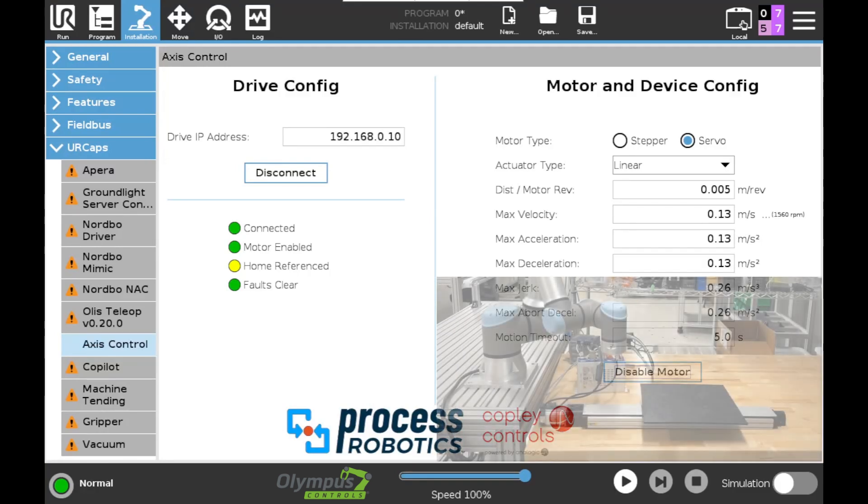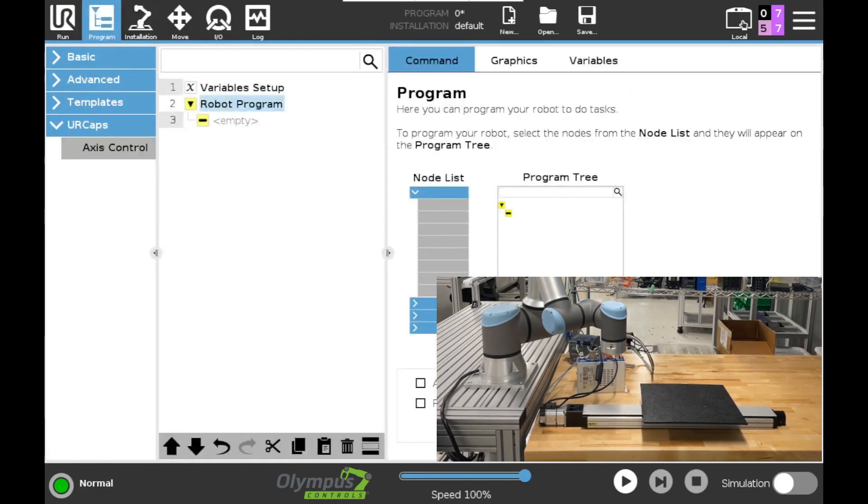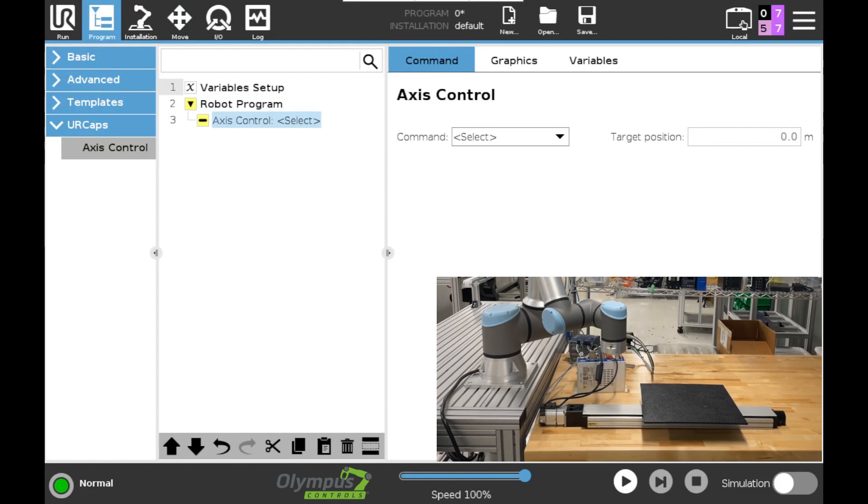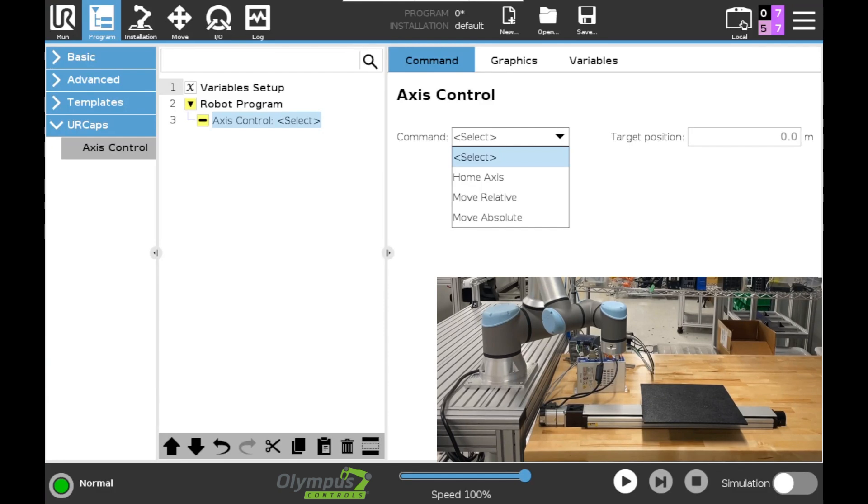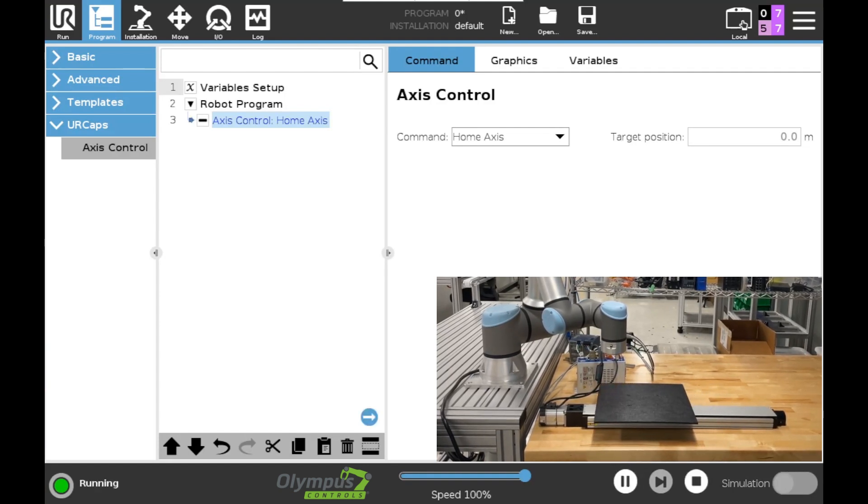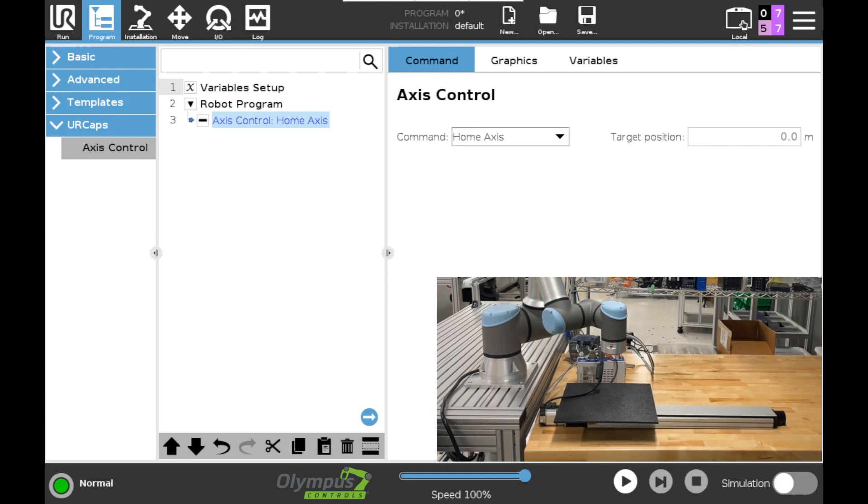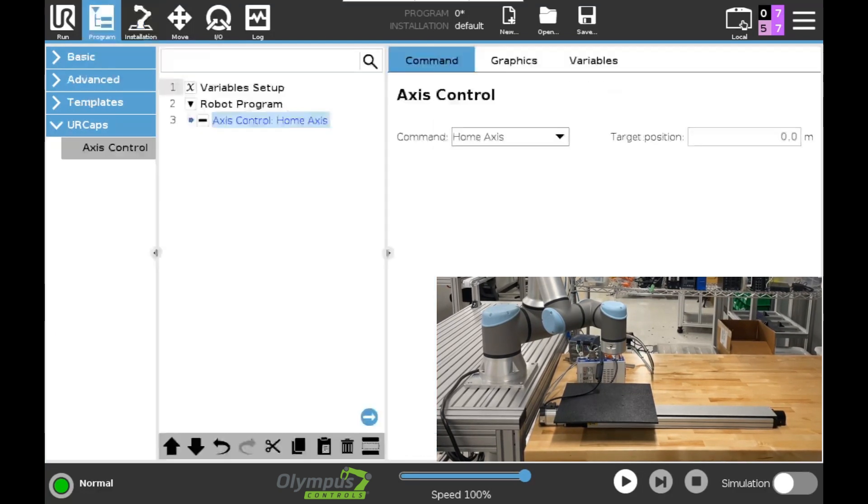In order to home the axis we'll need to actually start using our cap. And what the cap adds is a new node under the programming interface. You can see I've just added one into our blank program here. And you can see in our right panel this is what we are able to do. We can home the axis, move relative, move absolute. I know I want to home our axis and let's go ahead and play that. And our axis is referenced. If I go back into our installation tab I can see our home is referenced. We have no faults and we are ready to start commanding motion.